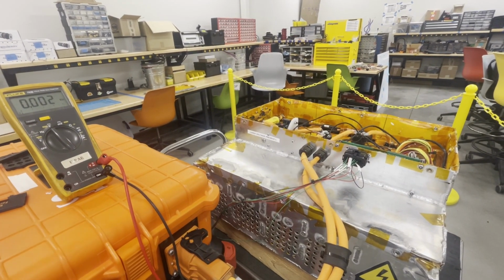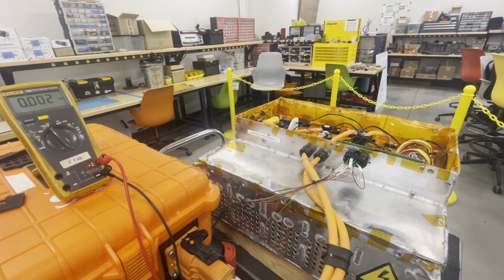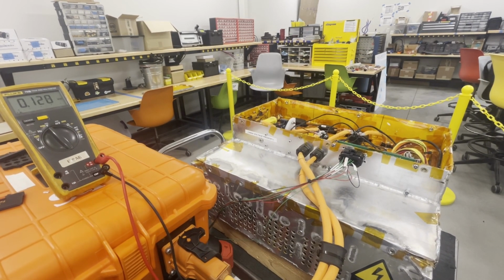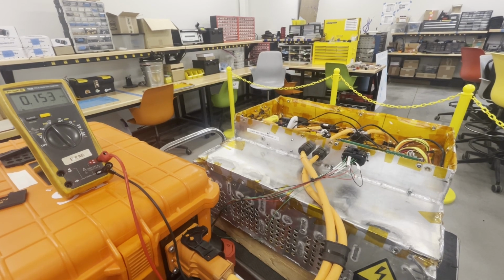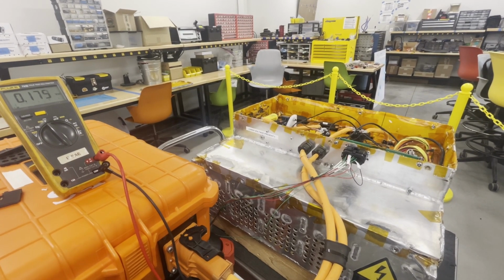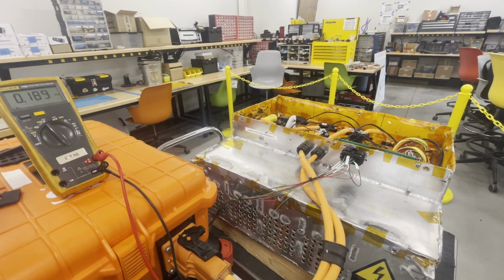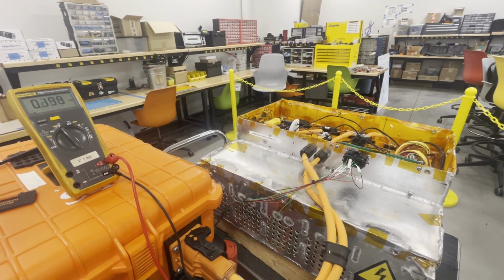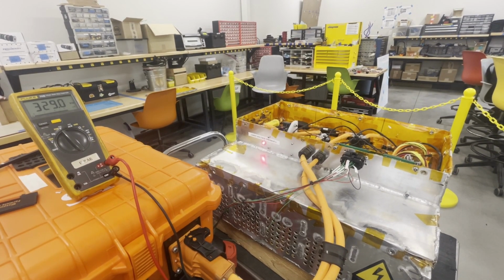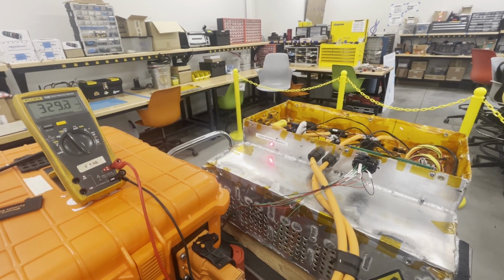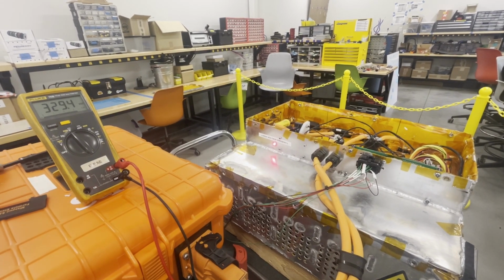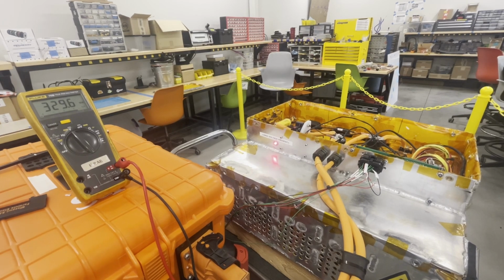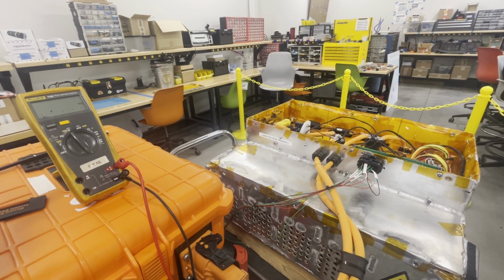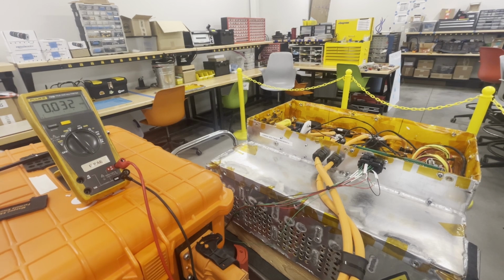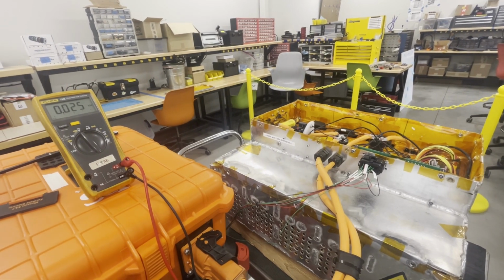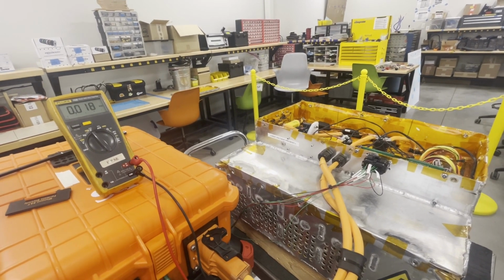Now, when we turn the low volt system on, the HVI does not come on because the contactors have not closed and we're not charging yet. Now what we'll do is we'll flip the charger on, and that contactor should close and the HVI should come on once we get above 60 volts on this multimeter. Do that, immediately at 329 volts, and the HVI is on. You can hear the fans come on the charger. Now we'll stop the charger, and once that goes below 60 volts, which it did, the HVI goes off, and there's no voltage outside the housing anymore.